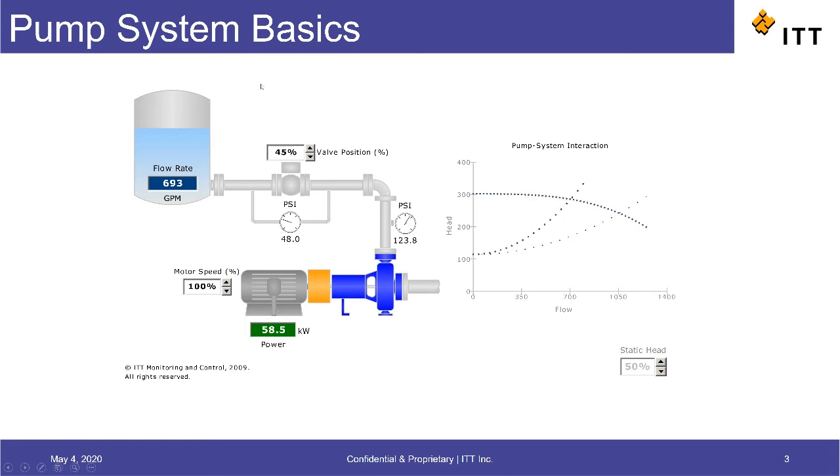The second way to control our pump flow rate is by altering the motor speed and therefore the pump speed using a VFD. Again, we're going to try to achieve that 700 gallons per minute. We're going to fully open up the discharge valve and then reduce the motor speed.